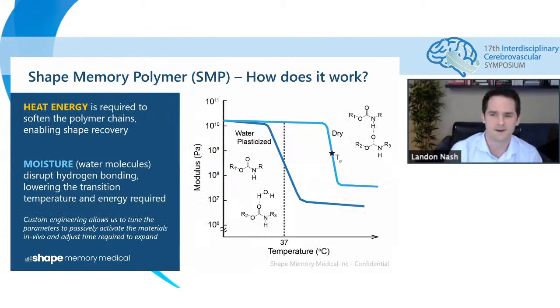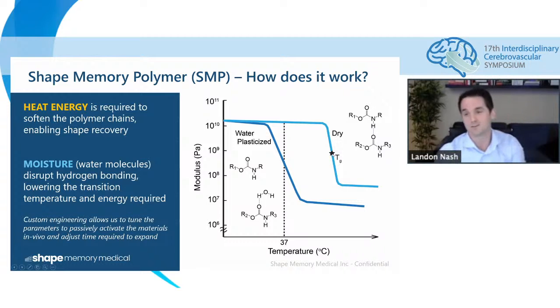Another thing I want to drive home is this mechanism requires heat and moisture, so both, not just one or the other. So this is a plot of the material stiffness versus temperature, and this inflection point is the temperature at which that polymer will expand. So when you first take it out of the package, it's dry and the transition is quite high. And then once you introduce it into the blood, over time, it will slowly plasticize over the indicated working time until that transition temperature is right at body temperature. And at that point, it can expand. So if you were to take these devices out and just saturate them in room temperature saline, even for an hour or several hours, it's not going to expand because you need that temperature input as well.